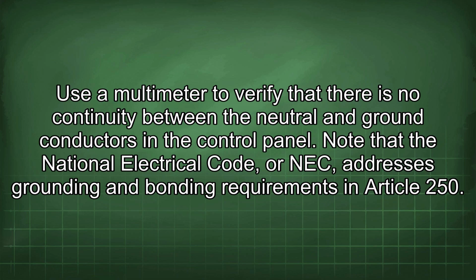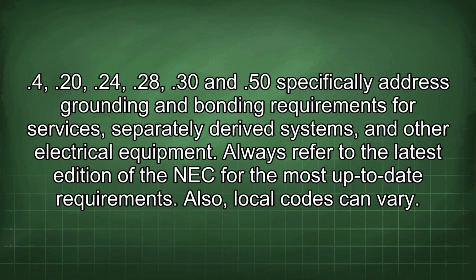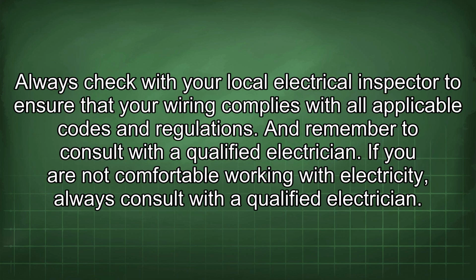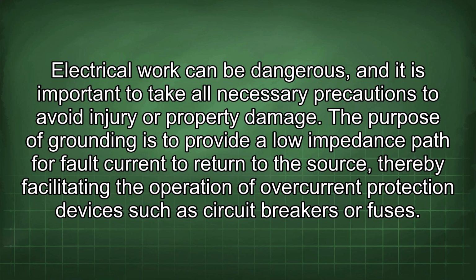Note that the National Electrical Code, or NEC, addresses grounding and bonding requirements in Article 250. Sections 250.4, 250.20, 250.24, 250.28, 250.30 and 250.50 specifically address grounding and bonding requirements for services, separately derived systems, and other electrical equipment. Always refer to the latest edition of the NEC for the most up-to-date requirements. Also, local codes can vary. Always check with your local electrical inspector to ensure that your wiring complies with all applicable codes and regulations. And remember to consult with a qualified electrician. If you are not comfortable working with electricity, always consult with a qualified electrician. Electrical work can be dangerous, and it is important to take all necessary precautions to avoid injury or property damage.